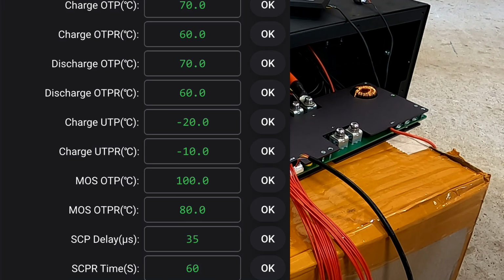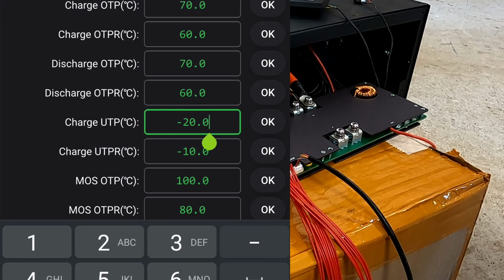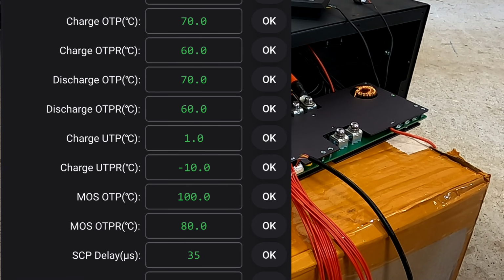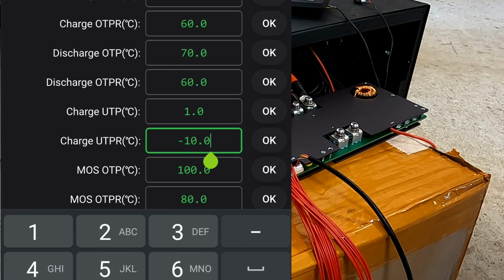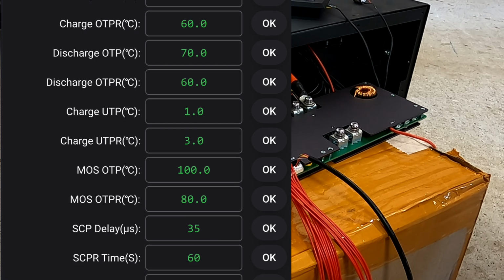And the only major concern here is the charge under temperature protection of -20 degrees. We should not charge the battery in negative temperatures anymore. So this setting here is completely wrong. I will report this back to JK. This should be at potentially 1 or 2 degrees. We're now getting an error because the recovery value just below needs to be higher. We set this one to 3 degrees. Set this one first, and then we can set our under temperature protection to 1 degree.